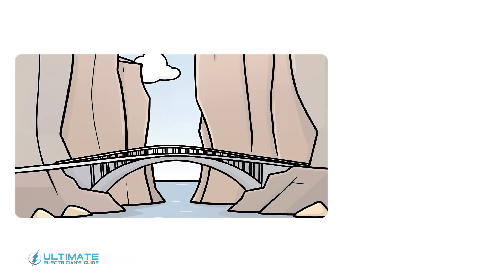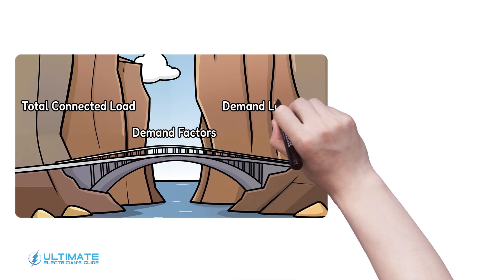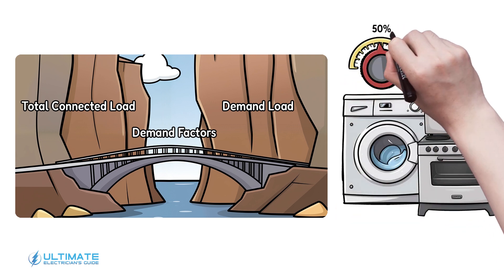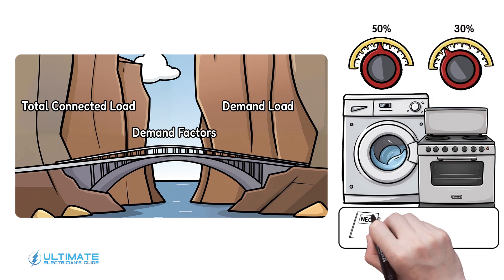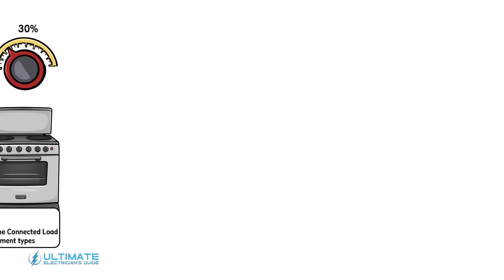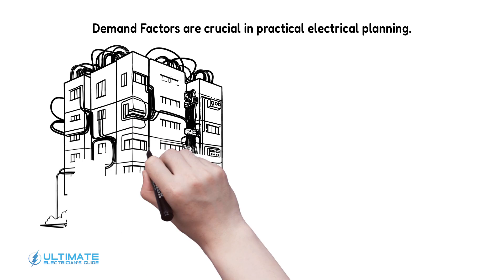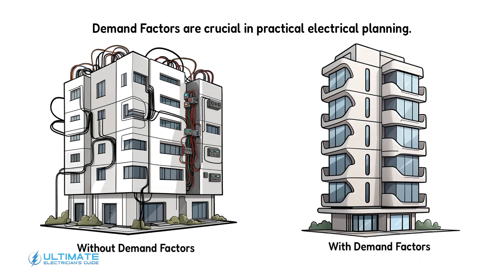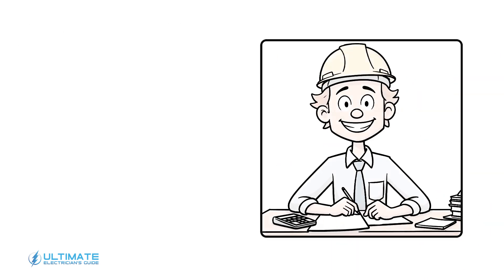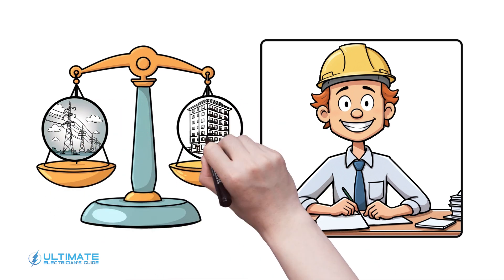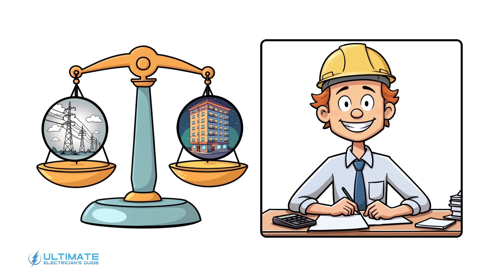Now, to bridge the gap between these two, we use what are known as demand factors. These are typically percentages set out in the NEC used to adjust the connected load of specific equipment types, such as clothes dryers or electric cooking appliances, to a more realistic figure. These demand factors are crucial in practical electrical planning. Without them, every building would have oversized and underutilized electrical systems, leading to unnecessary costs and inefficiencies. By applying these factors, we ensure that our electrical infrastructure is adequately sized — robust enough to handle the building's needs, yet not so large that resources are wasted.